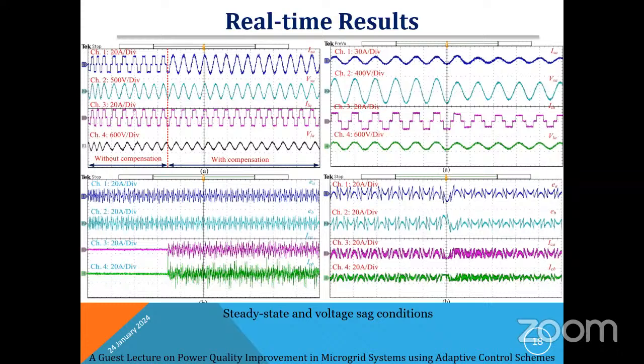platform. So if you see this first case, without compensation, the first one is current, second one voltage, third one load current, and finally load voltage. If you see before compensation, the current contains so many harmonics. After applying the controller, the harmonics are low after applying the control structure.